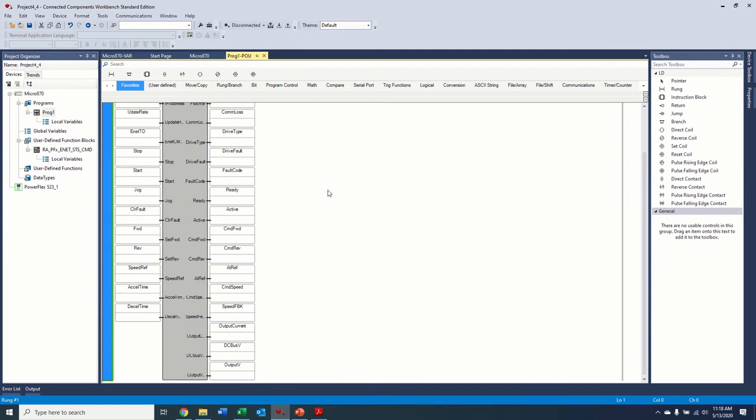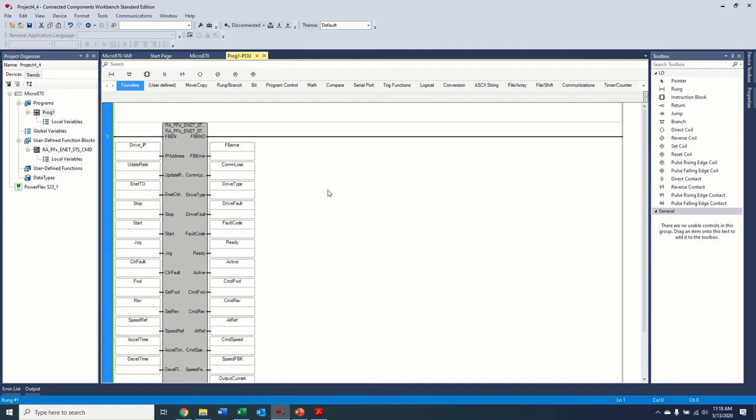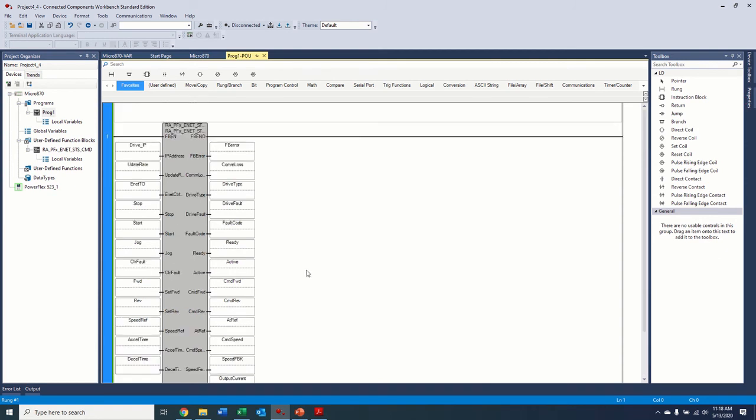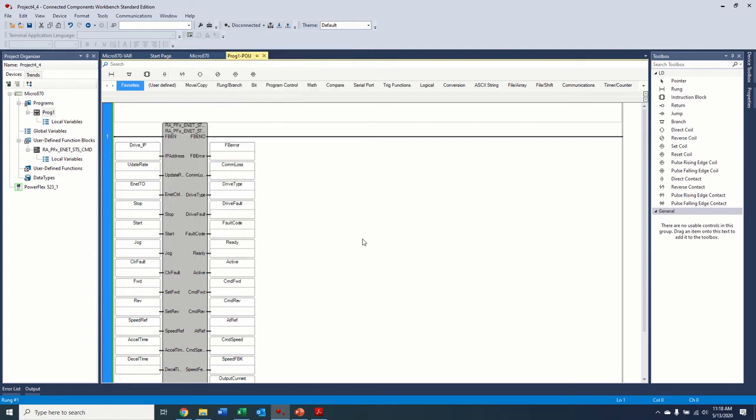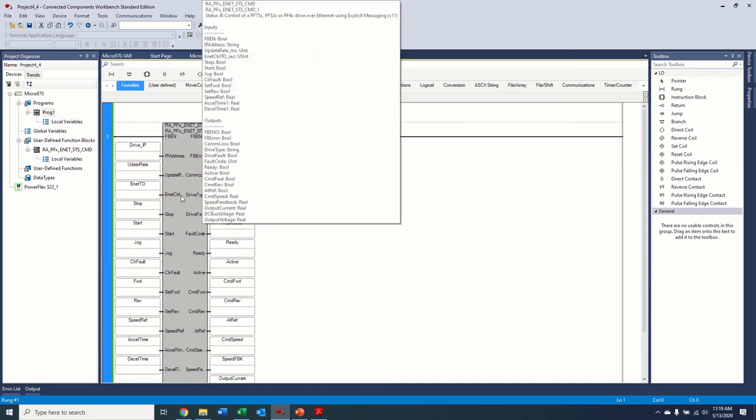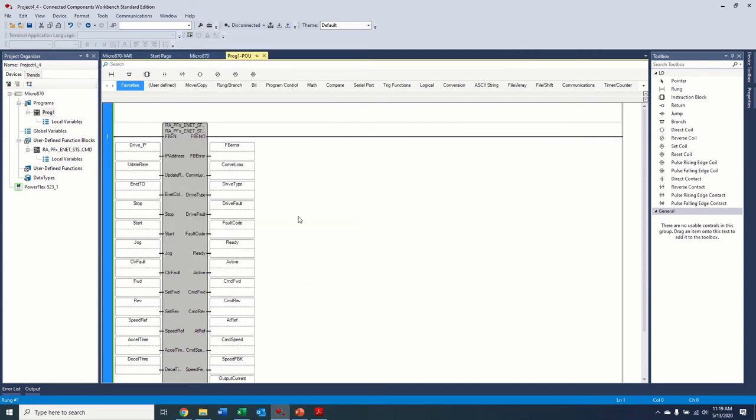Okay. So what I've done is I've gone offline with the controller and I've put tags in all of these points here so that we can control the drive and get everything out. Now you don't need to put a tag in each one of these. If you only want to start, stop the drive, clear a fault and know if it's running, then those are the tags you create. The only reason to create the tags is so you can get the information off to an operator through a touch screen or lights, things like that. So you need to be able to move that information from the block into a tag so that you can use it throughout the program. So that's the reason for doing it.